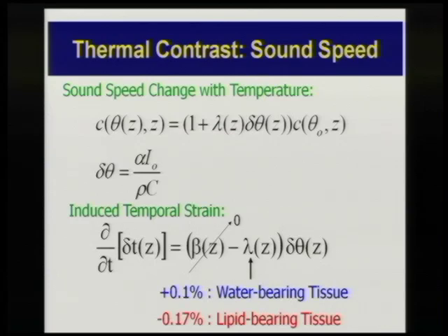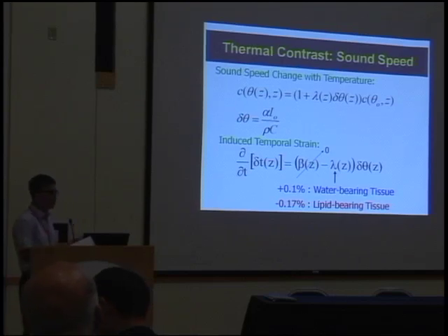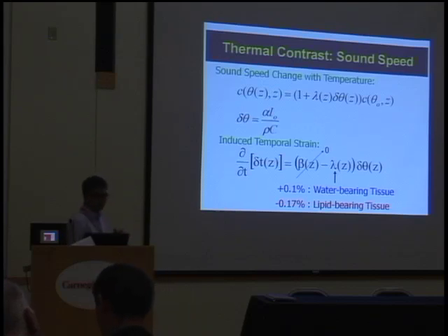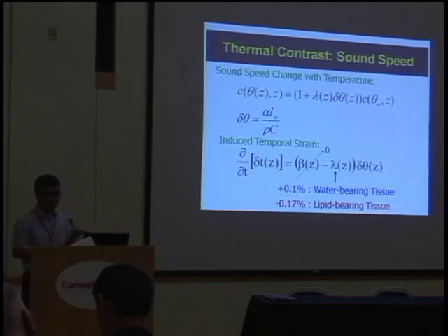As the temperature increases in the tissue, that generates sound speed changes that appear closer and further away, with a linear relationship to the temperature rise. We ignore the thermal expansion in the range of energy we use here, as we increase the temperature only 1 or 2 degrees Celsius, and we increase it very slowly.